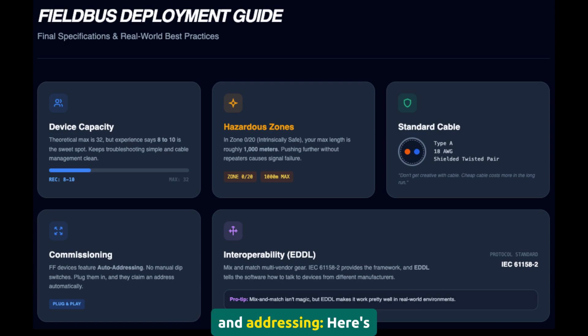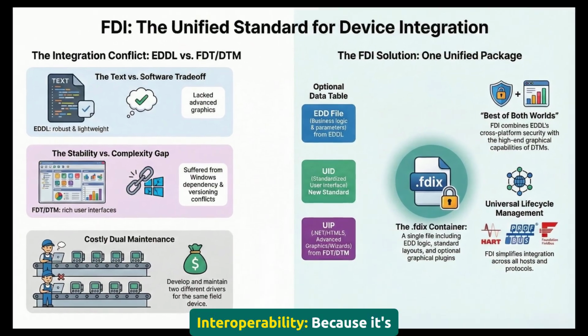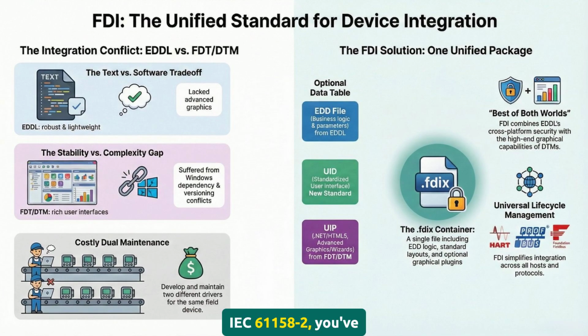Commissioning and addressing. Here's the lovely part. Foundation Fieldbus devices auto-address. You plug them in, they figure out what address to take. No manual dip switch configuration like the old days. That's actually elegant. Interoperability. Because it's IEC 61158-2, you've got multi-vendor gear that works together. Not always perfectly, welcome to real-world standards, but the framework's there. You can mix transmitters from different manufacturers on the same bus.